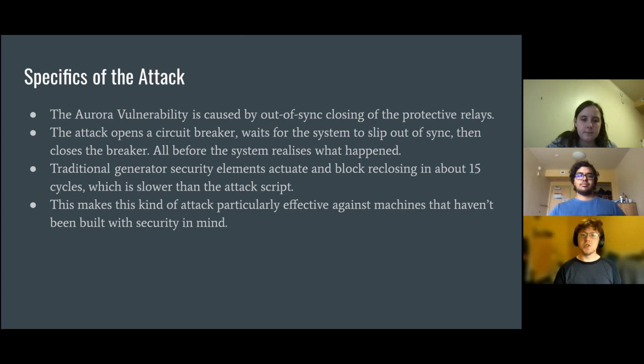Traditional generators normally regulate themselves, even without the protective relay, to ensure that if they detect anything wrong, they'll stop everything about every 15 cycles. This attack just makes sure it happens in less time than it takes the generator to go through 15 cycles, so the generator can't detect that something's wrong with itself. This makes this kind of attack particularly effective against machines that haven't been built with security in mind, because more frequent checking or another component watching for this would solve the issue.